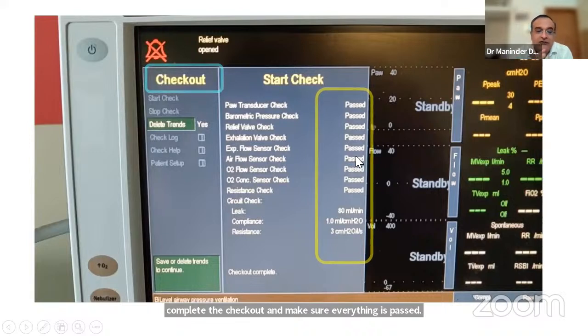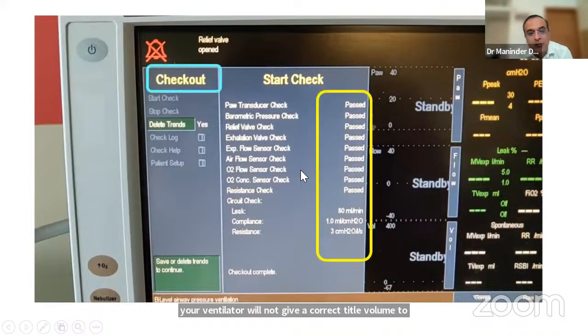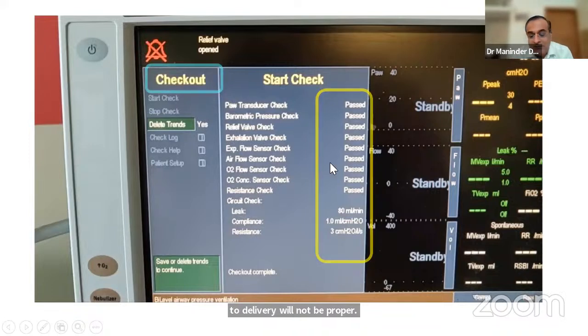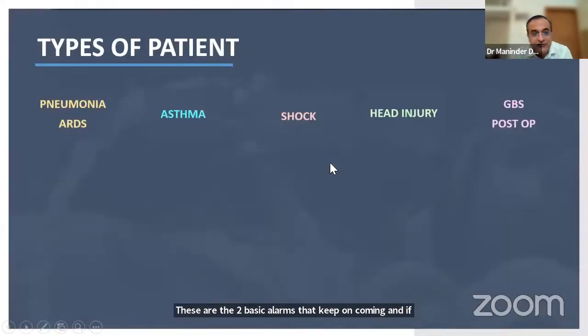That means your ventilator will not give a correct tidal volume to the patient. And if the oxygen sensor fails, then FiO2 delivery will not be proper. These are the two basic alarms that keep coming, and if you bypass them, it will be bad for the patient.